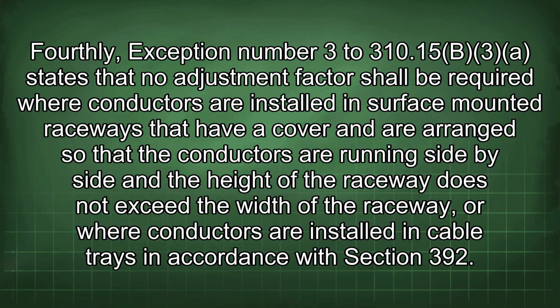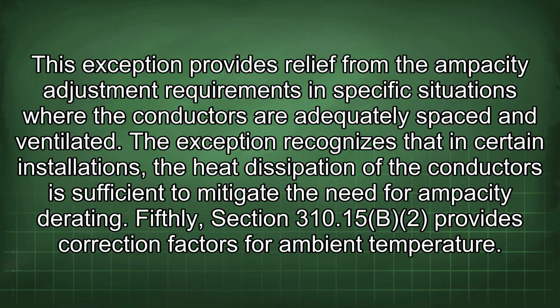Fourthly, exception number 3 to 310.15(b)(3)(a) states that no adjustment factor shall be required where conductors are installed in surface-mounted raceways that have a cover and are arranged so that the conductors are running side by side and the height of the raceway does not exceed the width of the raceway, or where conductors are installed in cable trays in accordance with Section 392. This exception provides relief from the ampacity adjustment requirements in specific situations where the conductors are adequately spaced and ventilated. The exception recognizes that in certain installations the heat dissipation of the conductors is sufficient to mitigate the need for ampacity derating.